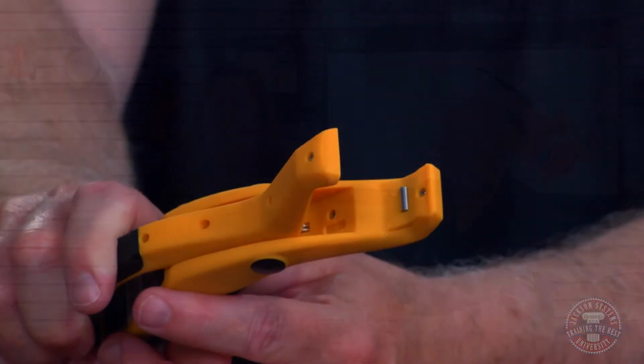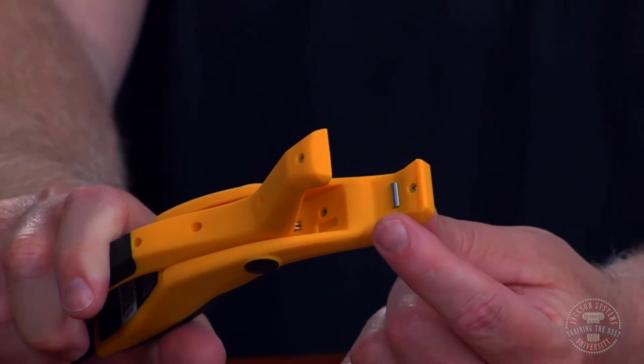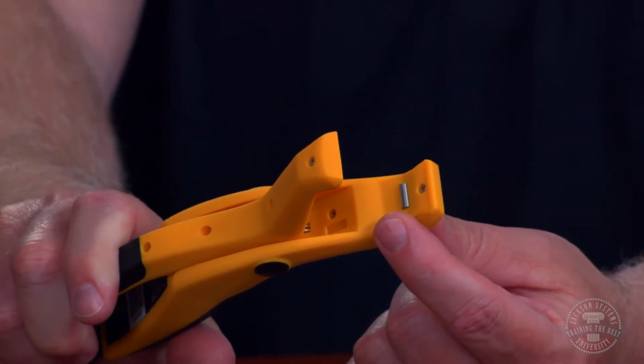The other thing that's a little different about this clamp - we're not going to be able to see inside, but this actually has a thermistor rather than a thermocouple, so that's going to give you a quicker response time. He's going to zoom in on that so you can see it's a thermistor style probe, which is typically a little more accurate and gives a faster response time than your traditional thermocouple.